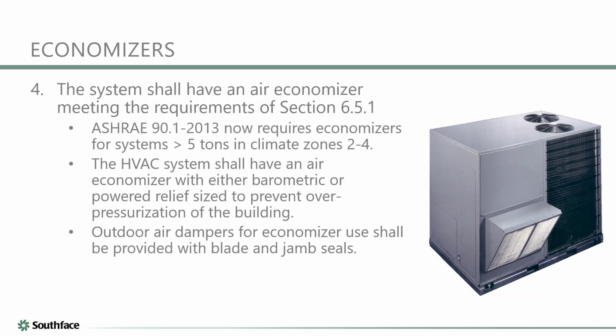So even within Georgia itself, you might have extreme North Georgia, places where they could probably use an economizer a couple hundred hours a year, and you go down to South Georgia and you might see some place where they're going to be able to use an economizer 20 hours a year, because they just don't have that many hours of their day when the building is occupied and the equipment is on that the outside air conditions really make economizers beneficial. And the cost of an economizer, putting in the equipment and the controls, might be something that a design team would want to look at not doing.